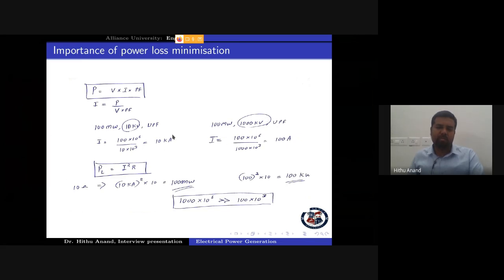Now we have another formula: power loss is given by I squared R, so we take the square of the current multiplied by the resistance. Assume a resistance of 10 ohms. At 10 kilo amperes, the power loss works out to 1000 megawatts. But when we substitute the current of 100 amperes, we get a power loss of only 100 kilowatts.